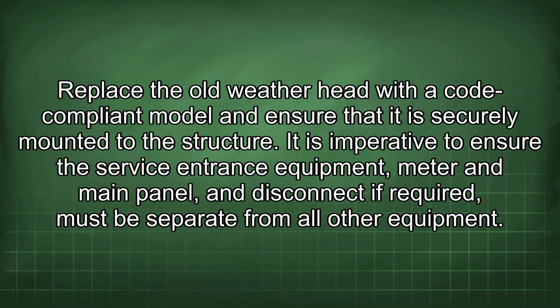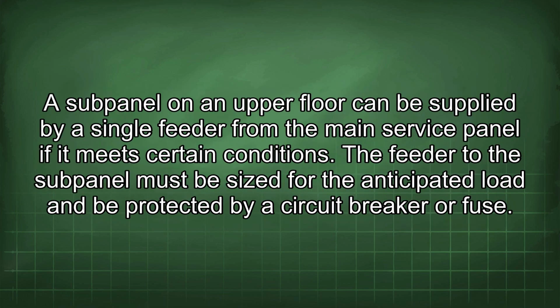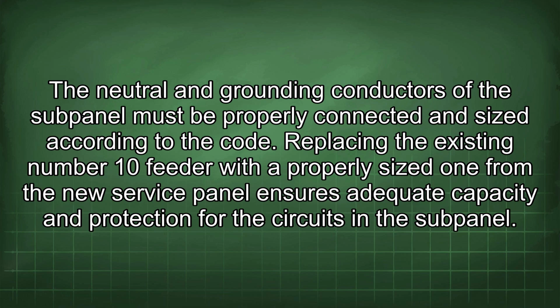It is imperative to ensure the service entrance equipment, meter and main panel, and disconnect if required, must be separate from all other equipment. A subpanel on an upper floor can be supplied by a single feeder from the main service panel if it meets certain conditions. The feeder to the subpanel must be sized for the anticipated load and be protected by a circuit breaker or fuse. The neutral and grounding conductors of the subpanel must be properly connected and sized according to the code.